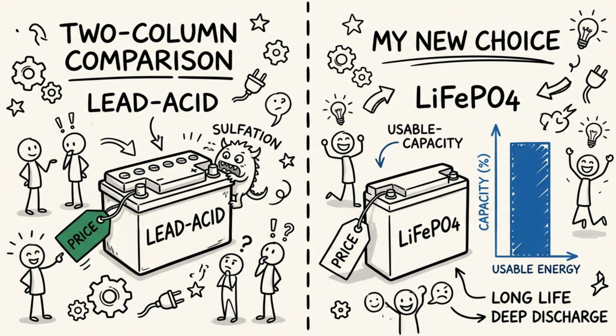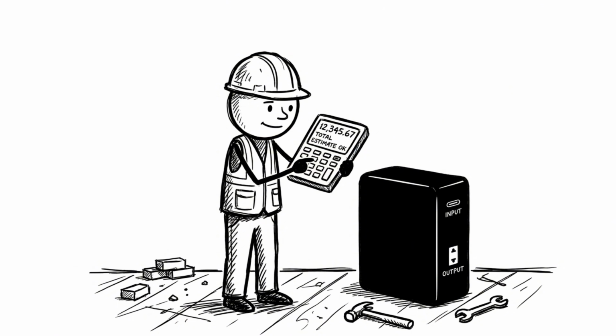The battery bank comes down to 2 practical families: lead-acid chemistries, flooded, gelled, or sealed AGM, the cheaper, well-understood default, and lithium iron phosphate, or LiFePO4, which costs more upfront but holds more usable capacity per pound and tolerates deeper discharges. Neither is a brand decision, it's a usable energy per dollar decision.